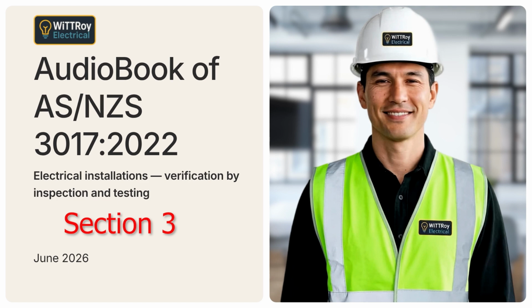For electrical equipment, isolation and switching devices must be checked where they are needed for protection against injury from mechanical movement. This can apply to motors and other equipment with moving parts. Isolation and switching devices must also be checked where they are needed for protection against thermal effects. This can apply to motors, room heaters, water heaters, and similar equipment. Switching devices for particular equipment must also be checked. Examples include socket outlets and water heaters.